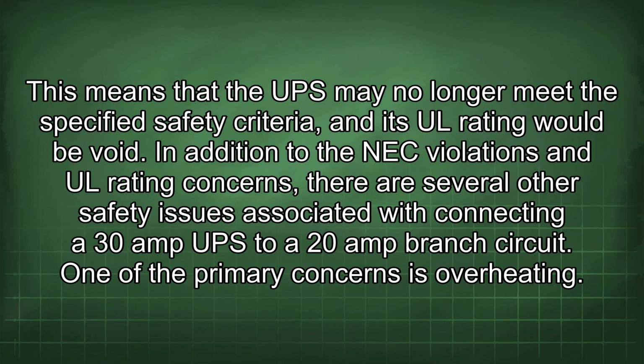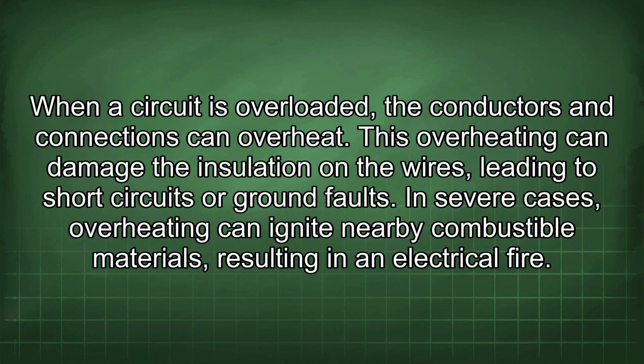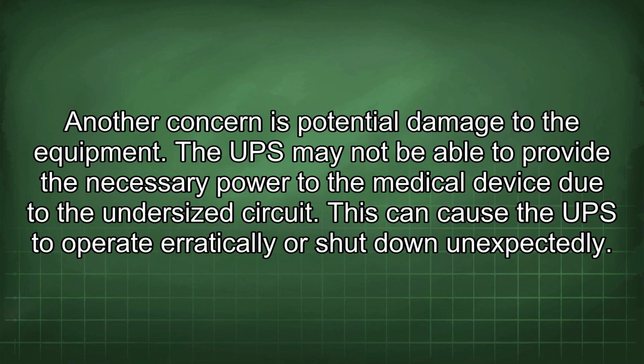In addition to the NEC violations and UL rating concerns, there are several other safety issues associated with connecting a 30 amp UPS to a 20 amp branch circuit. One of the primary concerns is overheating. When a circuit is overloaded, the conductors and connections can overheat. This overheating can damage the insulation on the wires, leading to short circuits or ground faults. In severe cases, overheating can ignite nearby combustible materials, resulting in an electrical fire. Another concern is potential damage to the equipment.